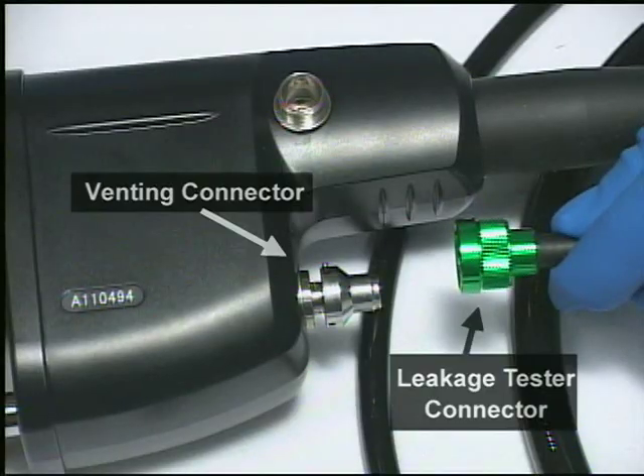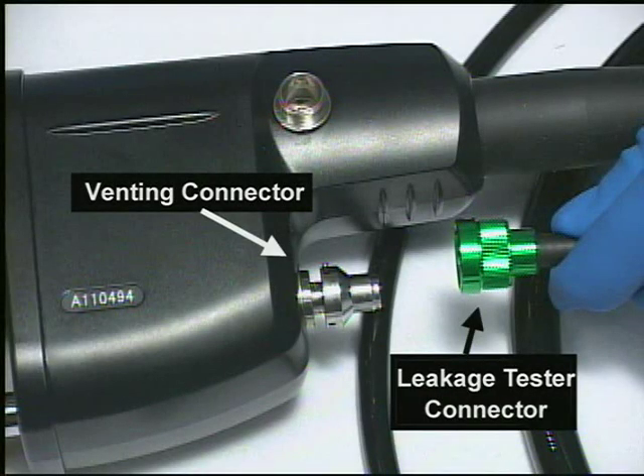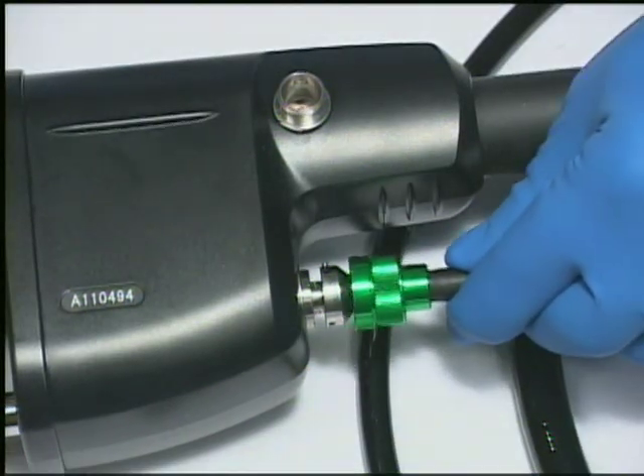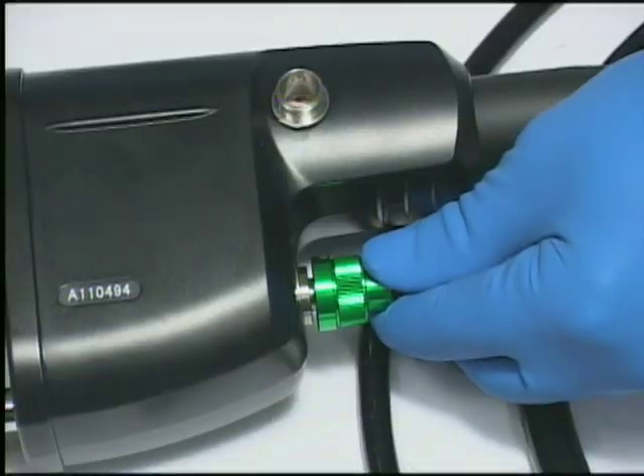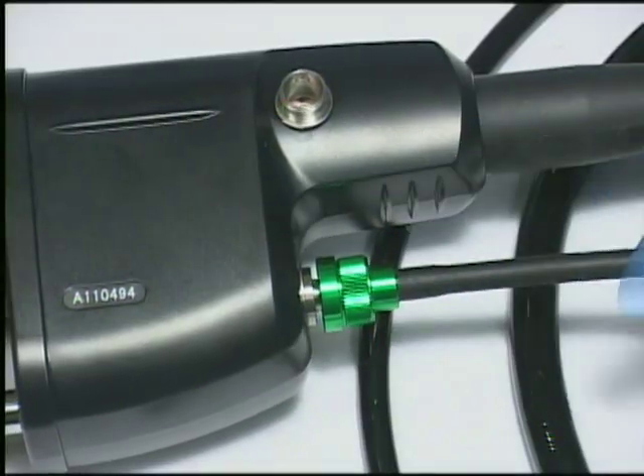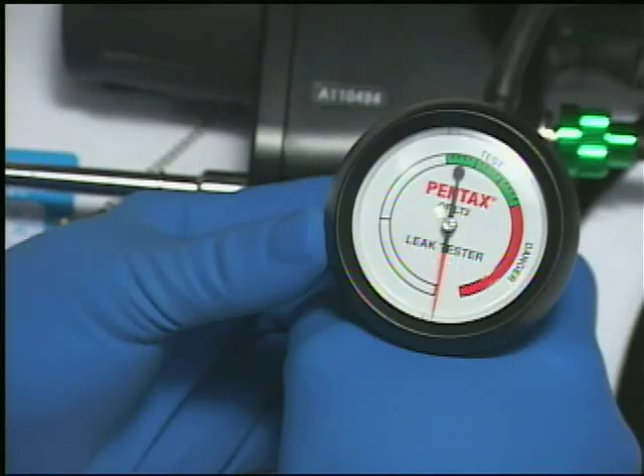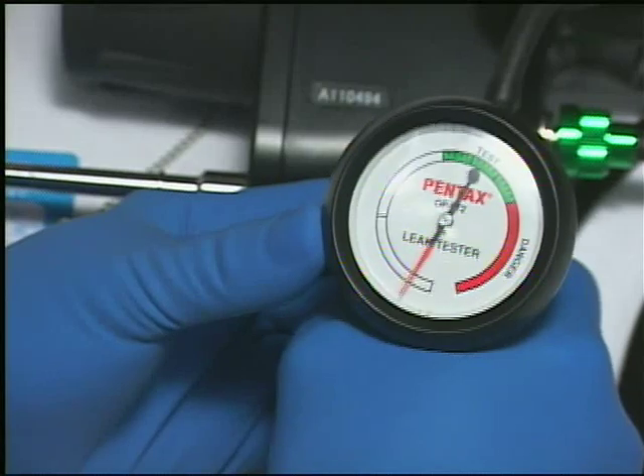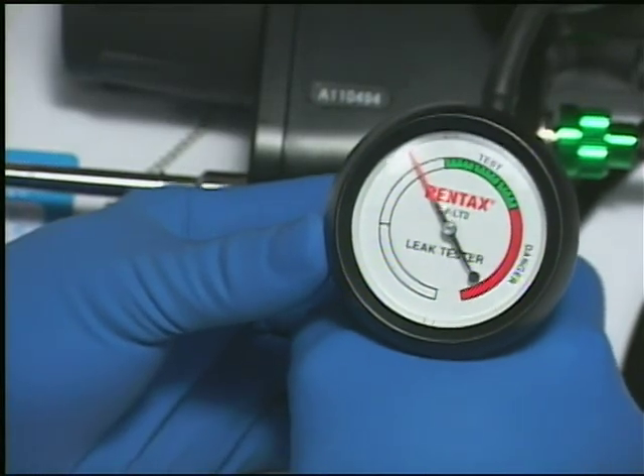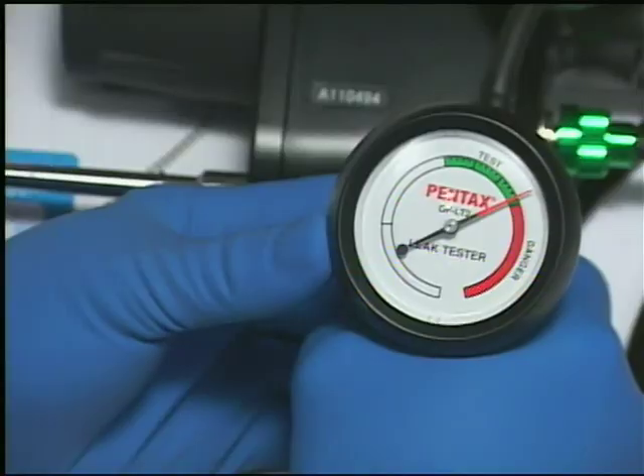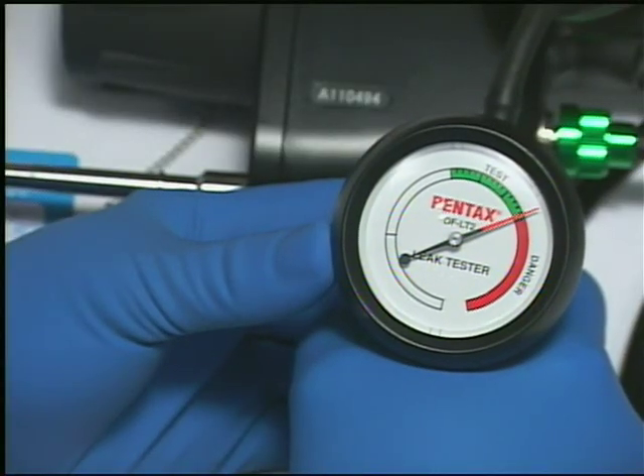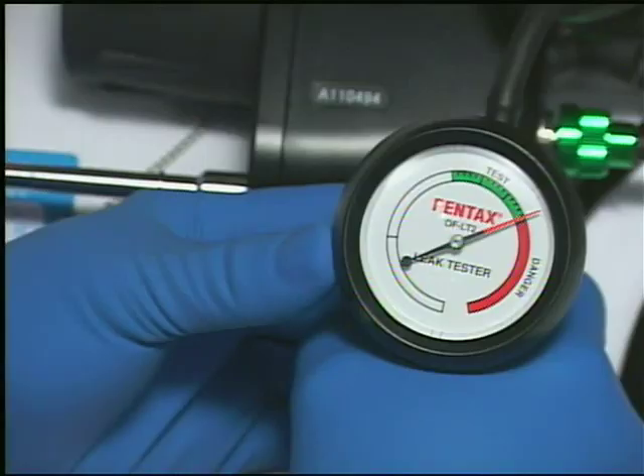Secure the leakage tester connector to the venting connector on the scope light guide. The leakage tester connector and the venting connector on the scope light guide must be dry before connecting. Proper connection will require alignment of the venting connector pin and clockwise rotation of the leakage tester connector. Ensure that the needle in the gauge is set to 0 and the pressure release mechanism is closed. Pressurize the scope by pumping the hand bulb until the indicator on the gauge is in the green zone. Do not pressurize into the red zone as it may cause serious damage to the scope.